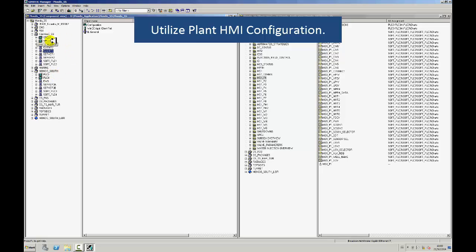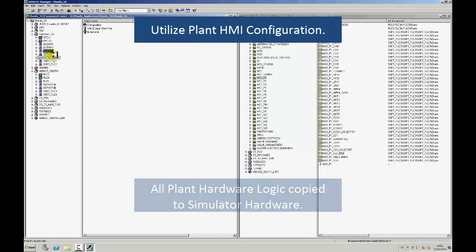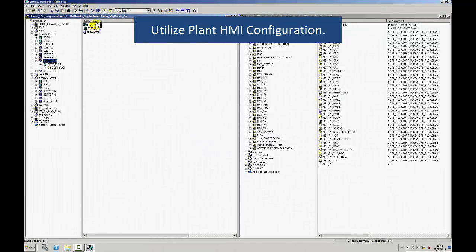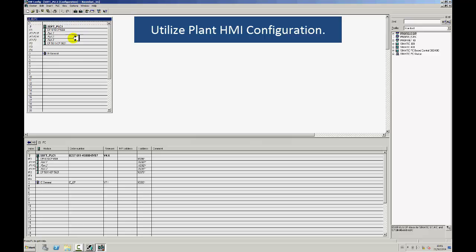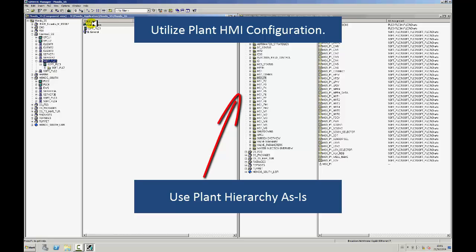On the left is a hardware component overview. If the training simulator uses soft PLCs instead of actual PLCs, we configure and copy the actual system configuration — including the data, function blocks, and charts — to the soft PLCs. The copy process is quite straightforward. On the right-hand side is the plant hierarchy view. You can see the actual plant hierarchy from the live system, which is what we copy across to the soft PLCs when we build the simulator.